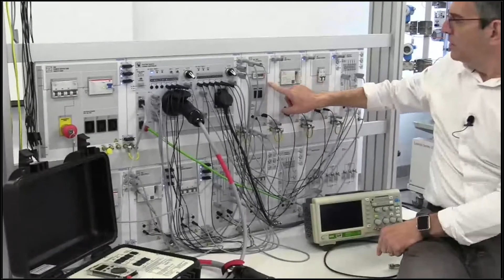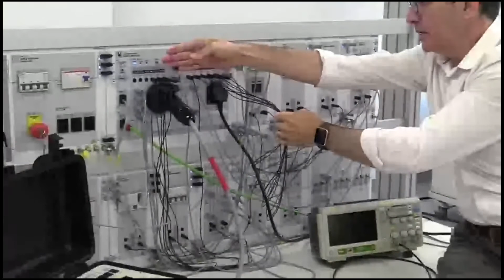From the meter, I go to the RCD, with two connectors, then jumpers to the circuit breaker, and finally to the 4-pole contactor. From the outlet of the 4-pole contactor, I have line 1 and neutral since we're in single phase, going back to the cables powering the plug to which the car will be plugged. So all of this is inserted between the power coming from the grid and the plug, to manage the safety aspect of the connection.